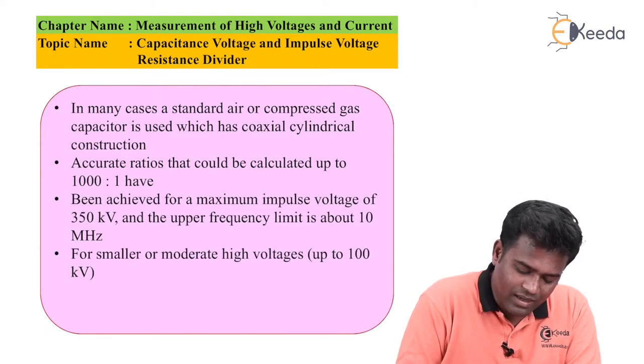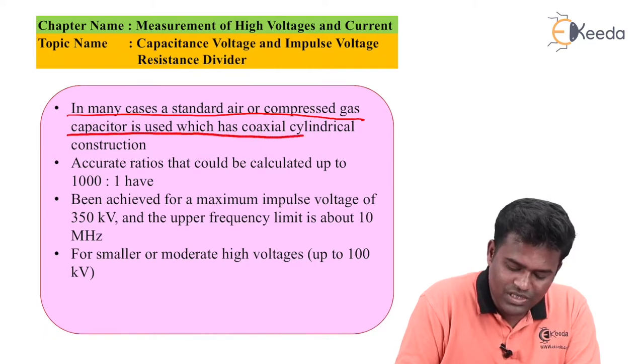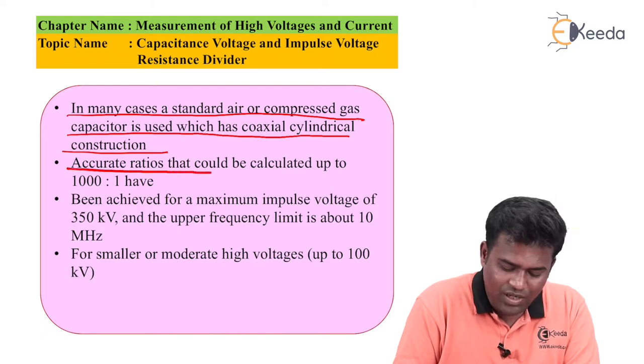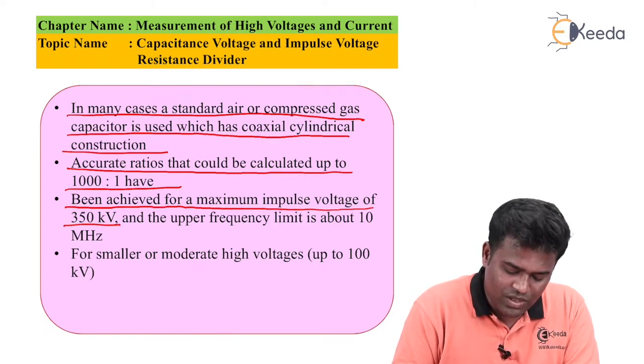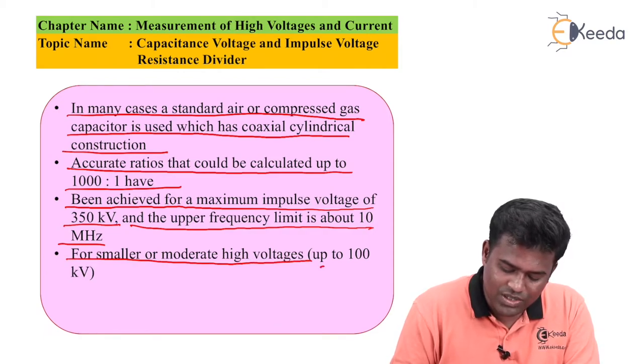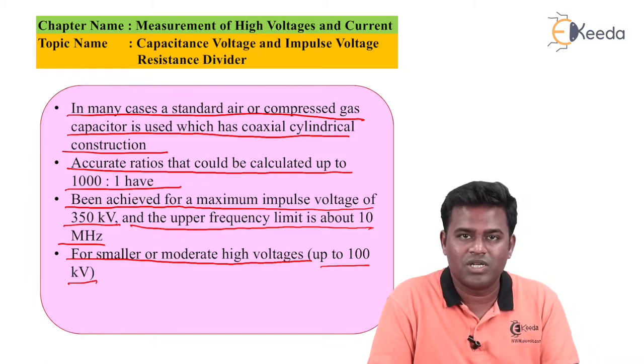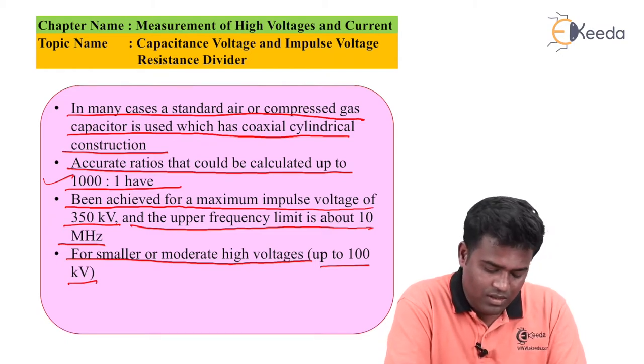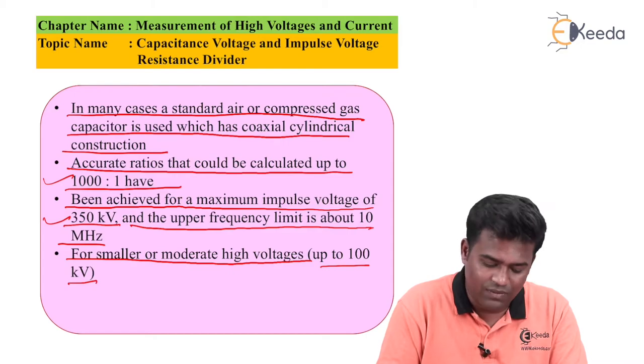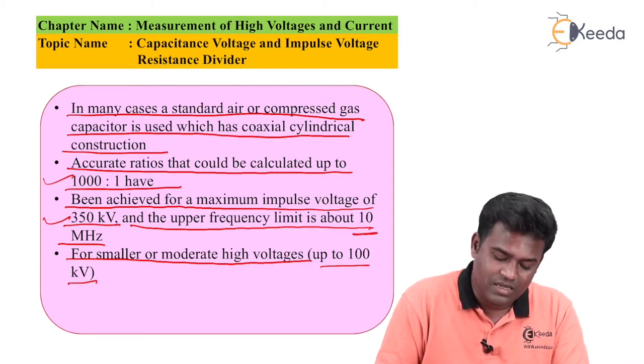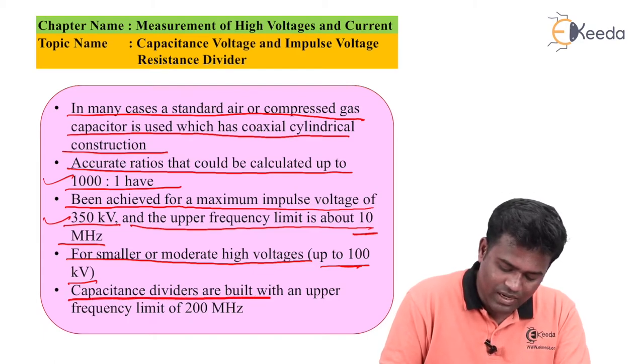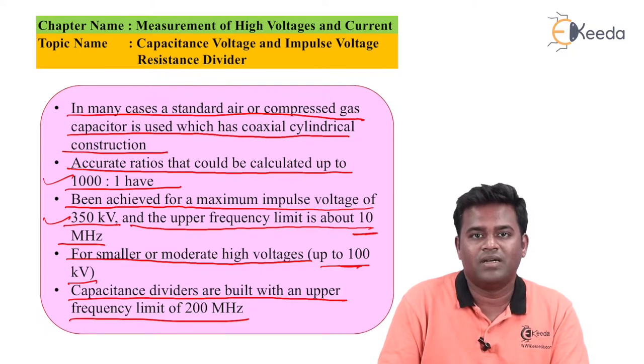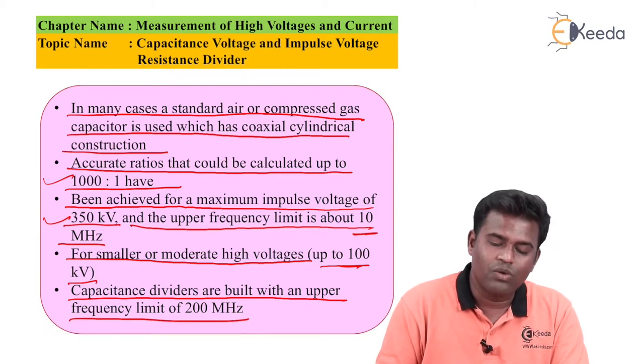In many cases, a standard air or compressed gas capacitor is used, which has coaxial cylinder construction. An accurate ratio that can be calculated up to 1000:1 can be achieved for a maximum impulse voltage of 350 kV, and the upper frequency limit is about 10 MHz for small or moderate high voltages up to 100 kV. These capacitance voltage dividers are used for a ratio of 1000:1, maximum impulse limit of 350 kV, frequency up to 10 MHz, and the capacitance dividers can be built with an upper frequency limit of 200 MHz.